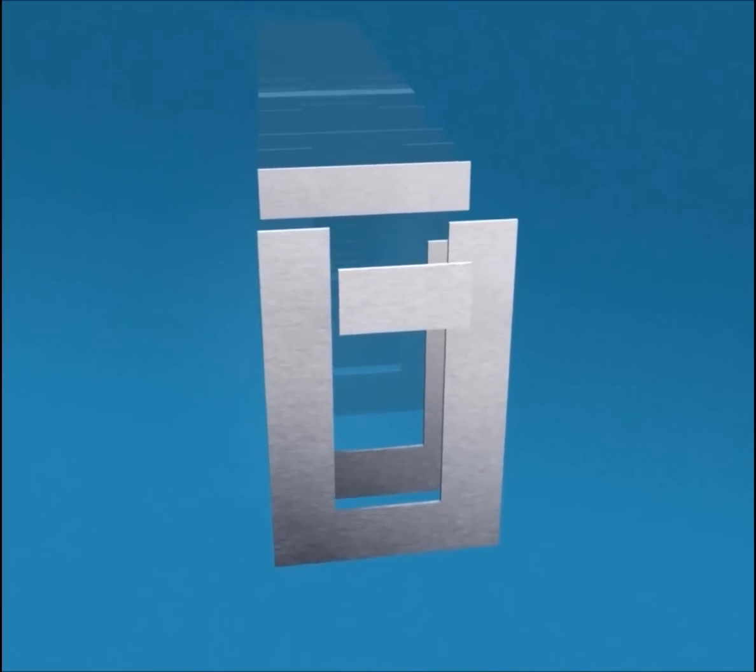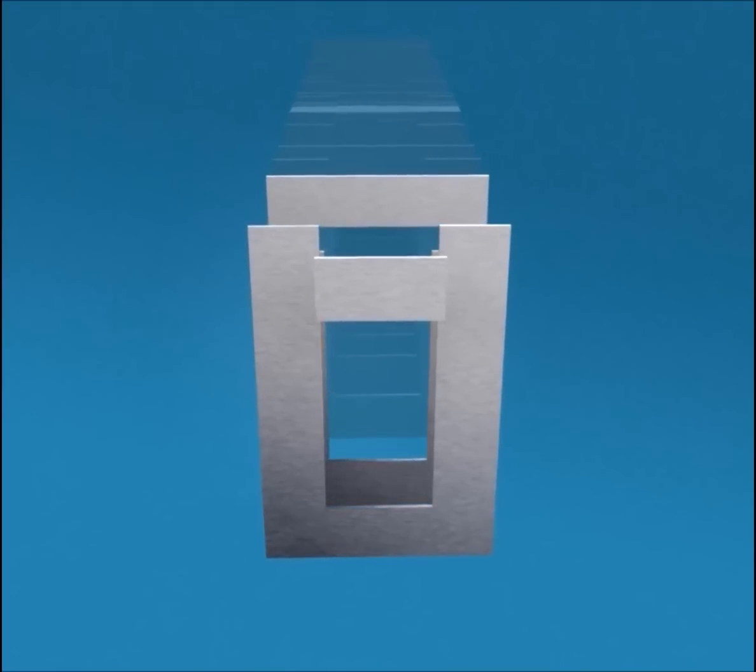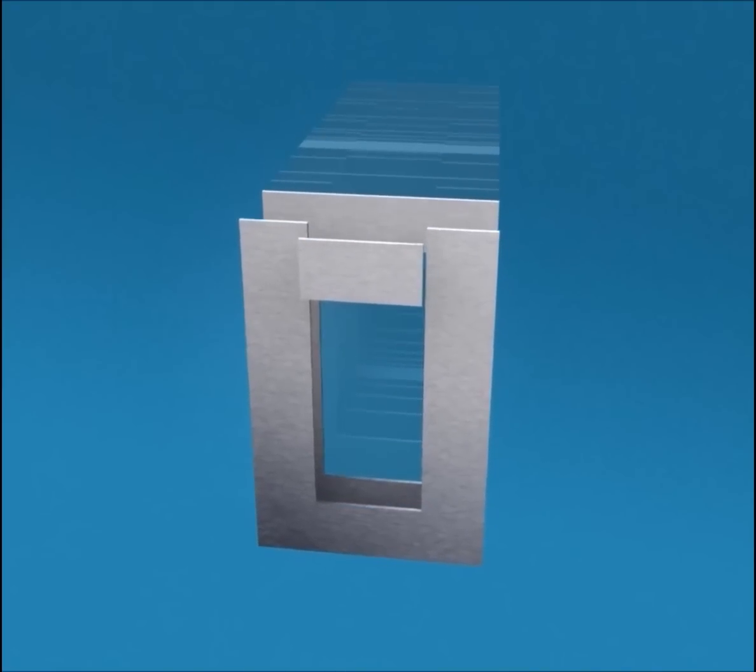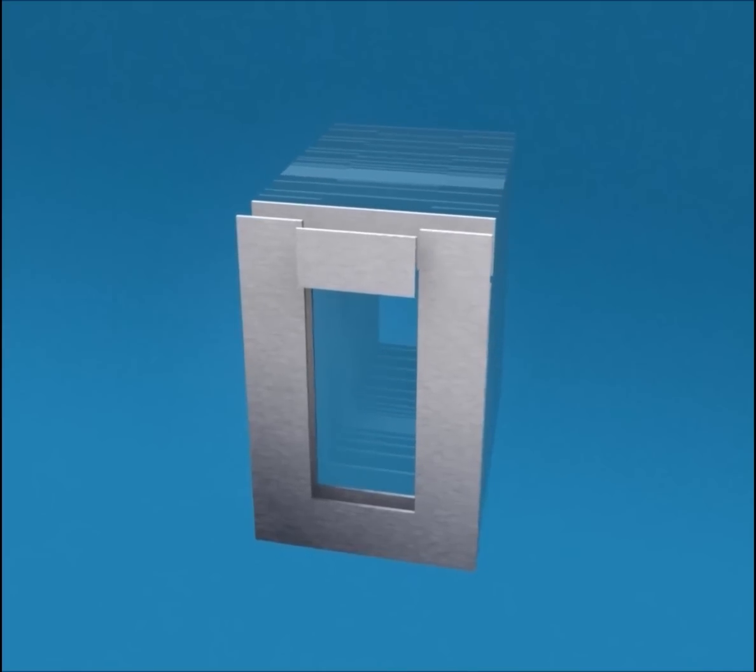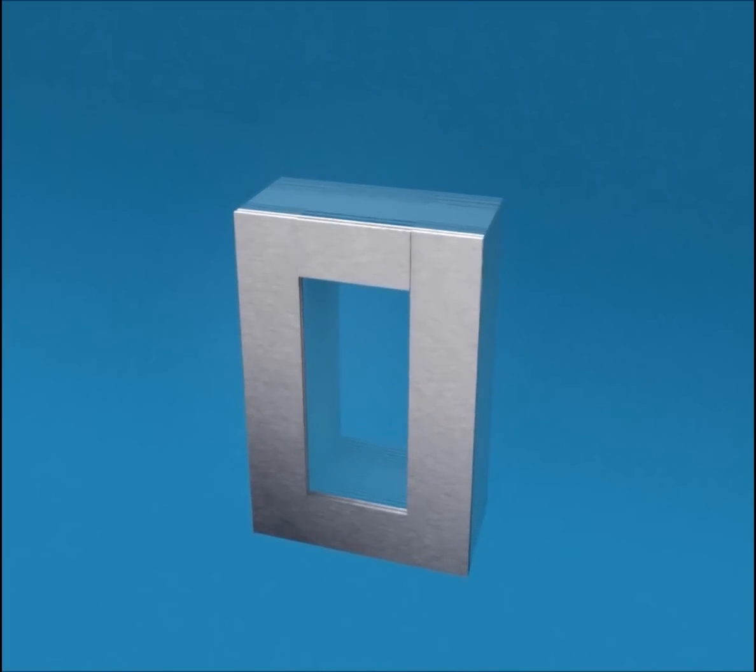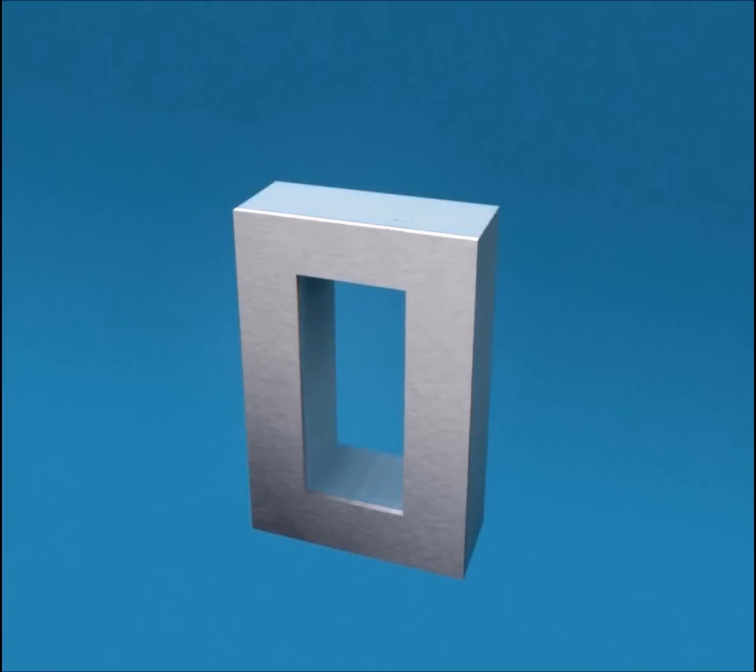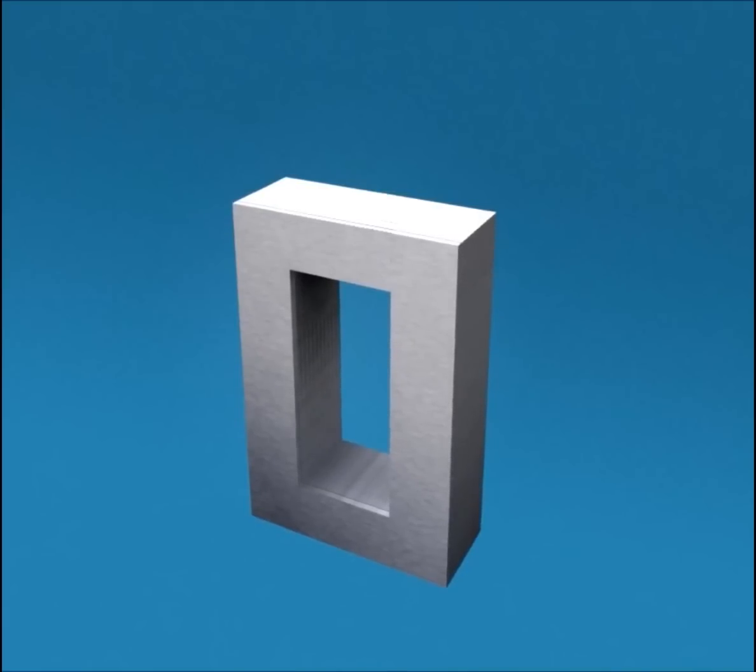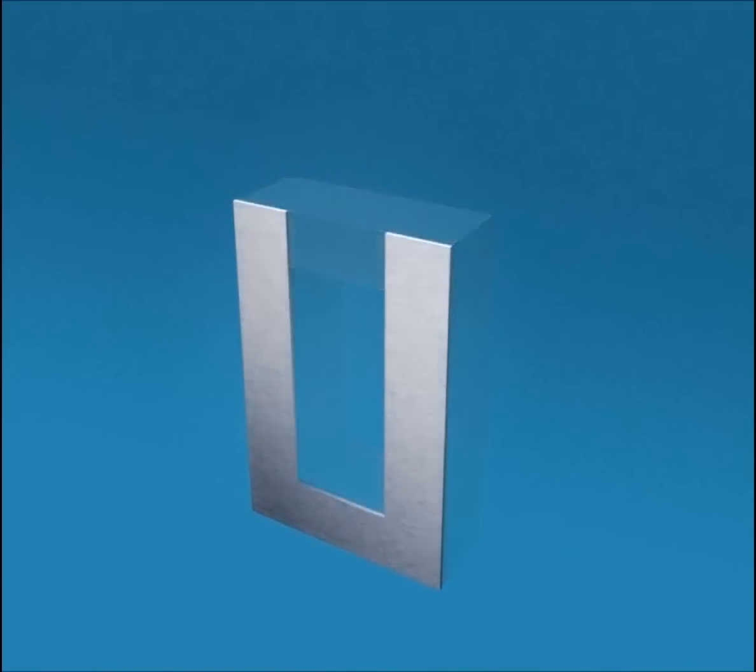To reduce these unwanted power losses, thin steel laminations are used to construct the transformer core. Laminations are made up of highly permeable material, that is silicon steel. These laminations are assembled together to build a solid core. The resistivity of the steel sheet itself is high, reducing the eddy current losses.